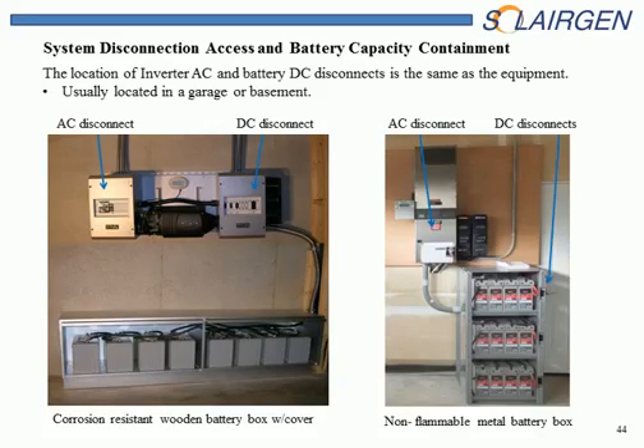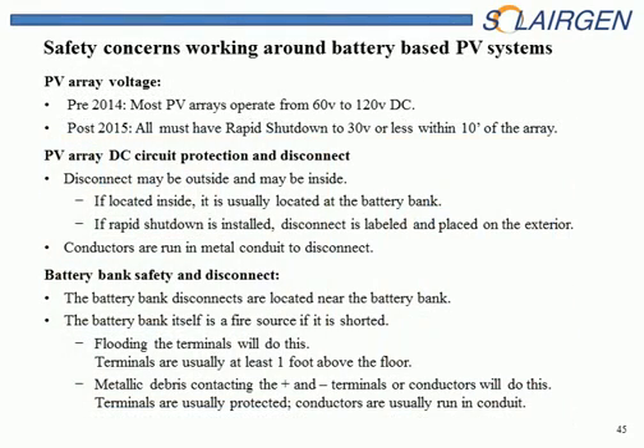The disconnect to disconnect the DC from the battery is usually up by the inverter. In this case it's down on the structure itself. These are disconnects on the battery structure. AC disconnect is in one of the panels next to it, and here it's in this panel and in this panel on this particular system. So garage or basement is the most likely place that you're going to see these battery systems. So let's review the safety concerns working around a battery-based system.